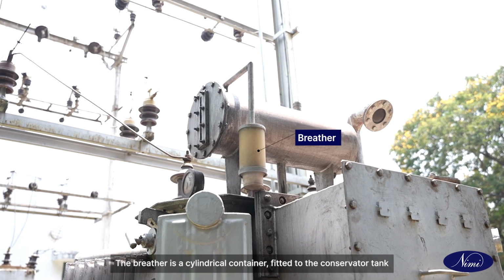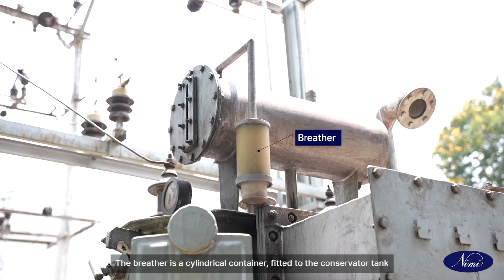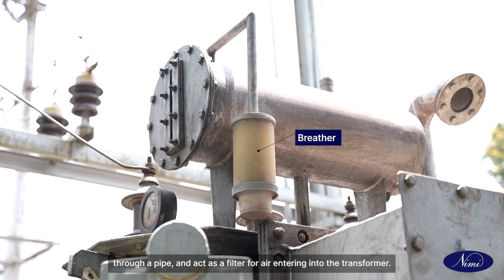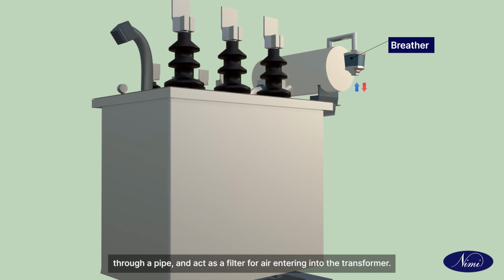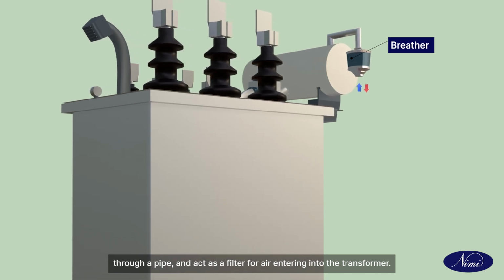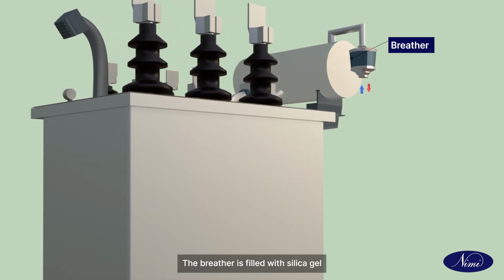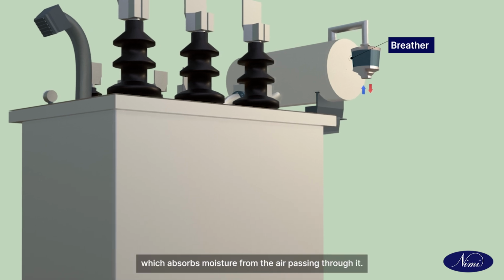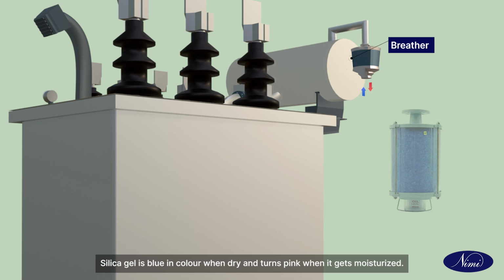The breather is a cylindrical container fitted to the conservator tank through a pipe and acts as a filter for air entering the transformer. The breather is filled with silica gel, which absorbs moisture from the air passing through it, so that only dry air can enter the tank. Silica gel is blue in color when dry and turns pink when it gets moisturized.